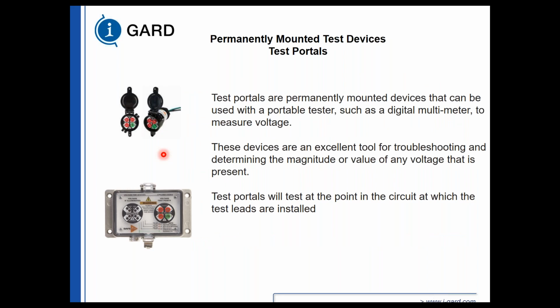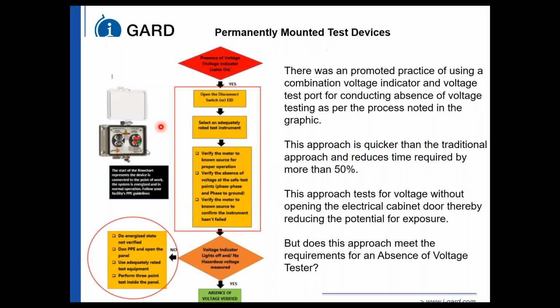So to compensate for the voltage detector LEDs, we put in test portals. Test portals are permanently mounted devices that can be used with a portable tester, such as a digital multimeter, to measure voltage. These devices are excellent tools for troubleshooting. If you want to do phase-to-phase testing and phase-to-ground testing, they can be used for that. However, they should not be used for absence of voltage testing, because the only thing you can verify by testing one of these devices is that there's no voltage present at these terminals. We haven't really deemed the gear to be de-energized.